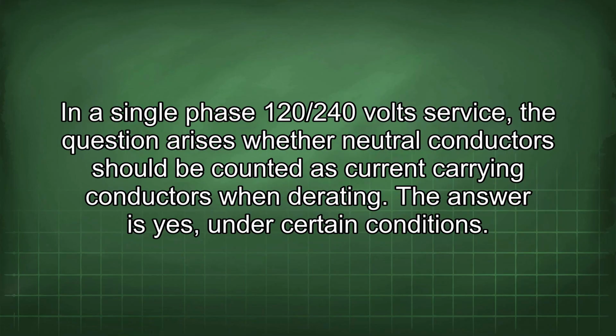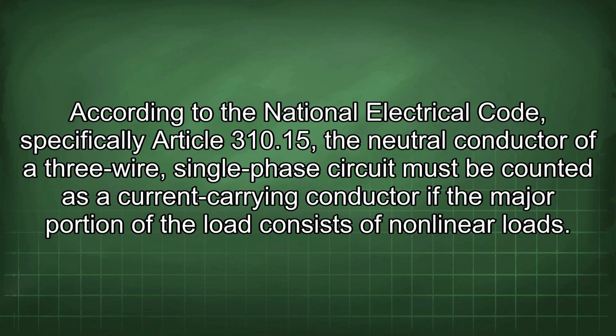In a single-phase 120/240 volt service, the question arises whether neutral conductors should be counted as current-carrying conductors when derating. The answer is yes, under certain conditions. According to the National Electrical Code, specifically Article 310.15, the neutral conductor of a 3-wire, single-phase circuit must be counted as a current-carrying conductor if the major portion of the load consists of nonlinear loads.